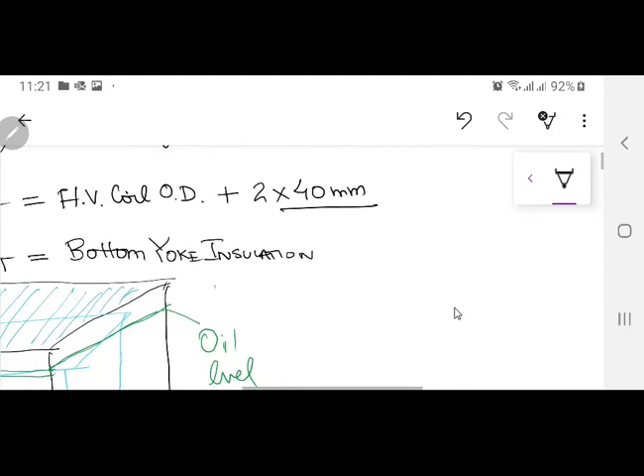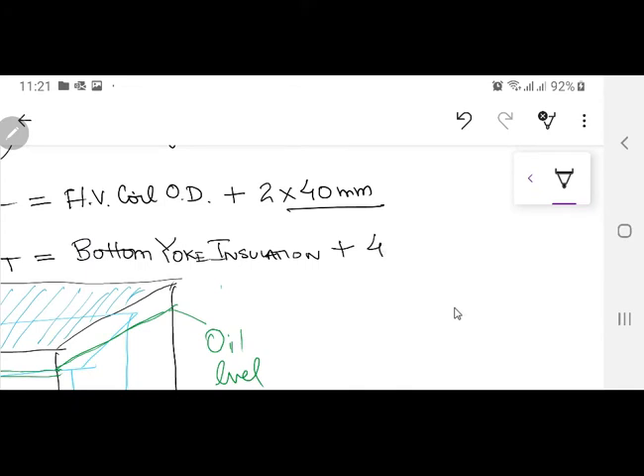Last thing, height. As I told you, there is going to be some wooden block or asbestos material placed on the below part. Over here they have taken this as approximately, without giving it a name, they have called it the bottom yoke insulation. And then a clearance distance of 40 mm.